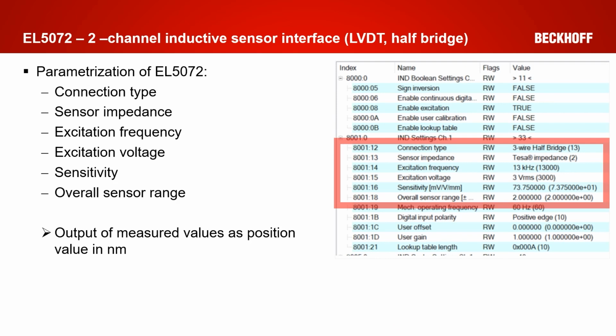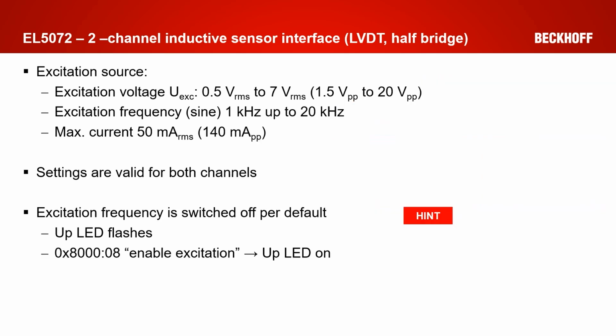Now we can check the excitation frequency and the excitation voltage parameters. The terminal has an excitation source that can be set in a wide range of voltages between 0.5 up to 7 VRMS, and also a wide range of frequencies between 1 kHz up to 20 kHz with a maximal current of 50 milliamps. If you do not find the desired voltage or frequency in the available lookup table entries, it is recommended to select the closest value, if possible. We have made the experience that thereby a slight deviation in the measurement range occurs. This can be corrected by user adjustment.